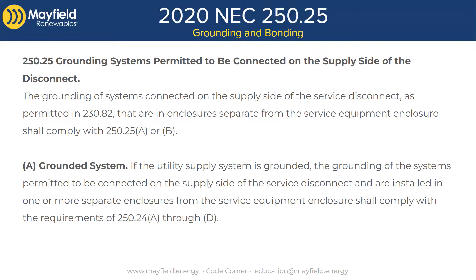In short, 250.25 says that when we have systems connected to the supply side of the service disconnect, we have to comply with subsection A or B. A covers grounded systems, B covers ungrounded systems. For our typical electrical systems, they're going to be grounded systems. And 250.25A basically points us to 250.24A through D. There's not a whole lot new here because 250.24 was already there, but we have a nice section saying go look at this very specific section.